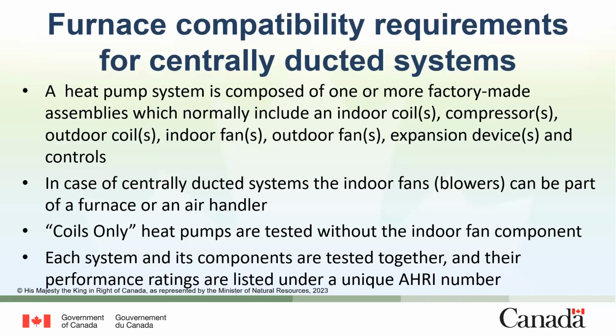We received a lot of questions about furnace compatibility requirements for centrally ducted systems. I want to clarify that a heat pump system is composed of one or more factory-made assemblies, which normally include an indoor coil, compressor, outdoor coil, indoor fan, outdoor fan, expansion device, and controls. For centrally ducted systems, the indoor fan blower can be part of a furnace or an air handler, so most heat pumps are rated with the indoor fan component, and their performance is listed in industry directories along with the indoor coil, outdoor coil, and the furnace or air handler they were tested with.